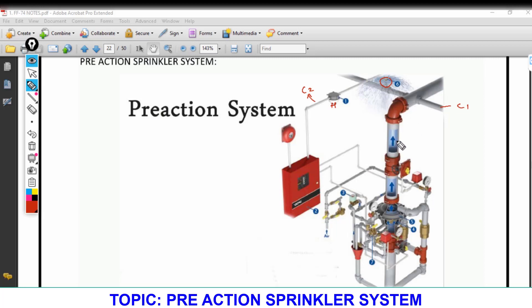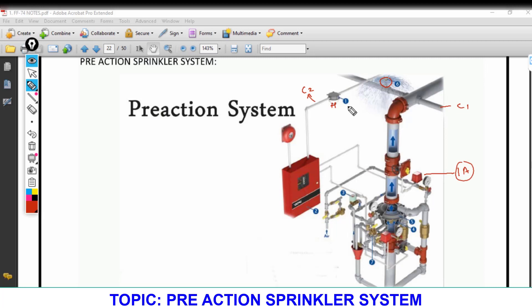If the sprinkler is damaged accidentally, since it is a dry system, only the compressed gas will release. This release of compressed gas activates only the initial alarm — a smaller alarm for maintenance purposes — so maintenance people can replace the damaged sprinkler. Importantly, the water will not supply; the valve will not open and the system will not fully activate.